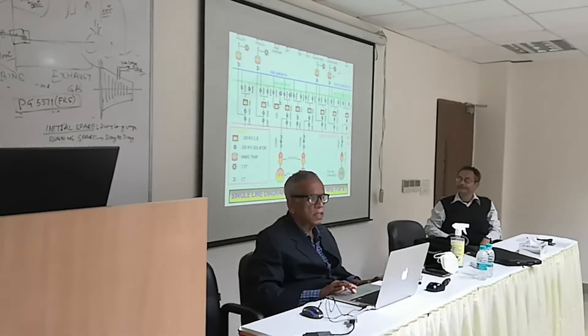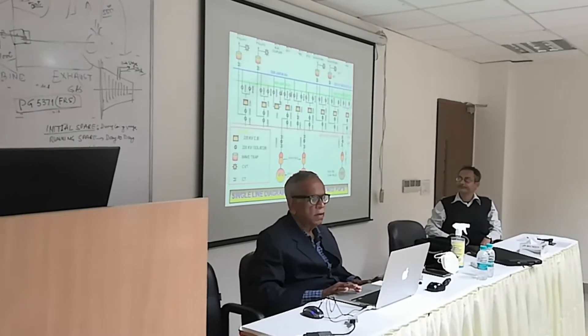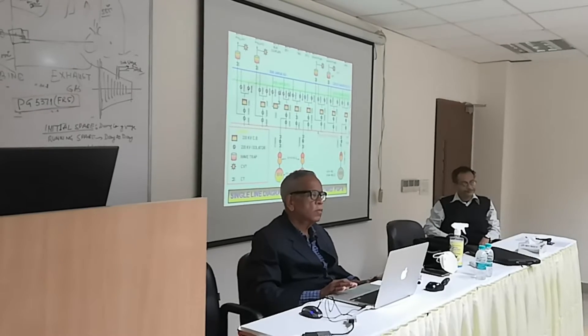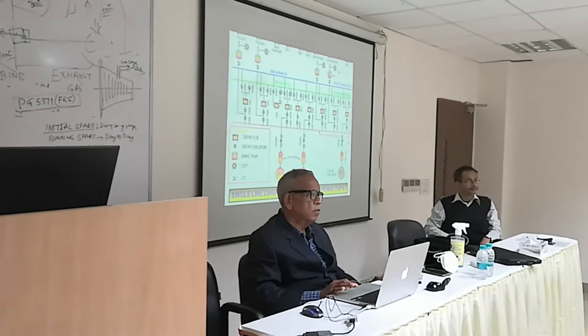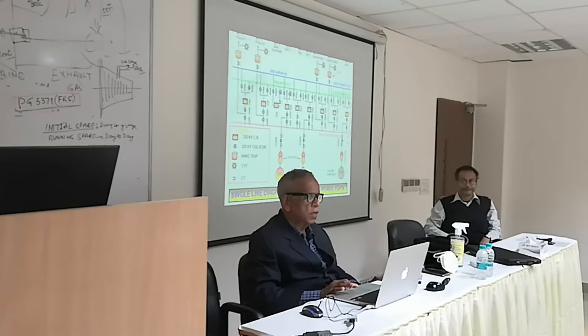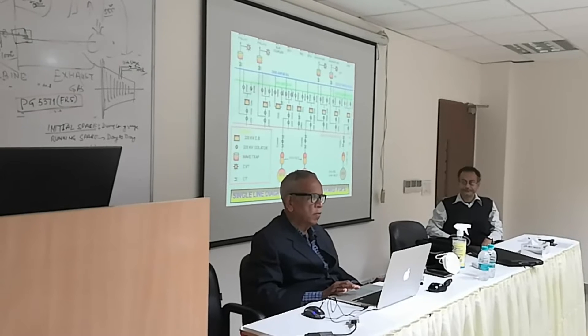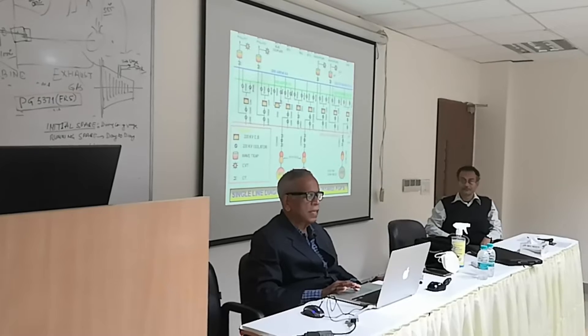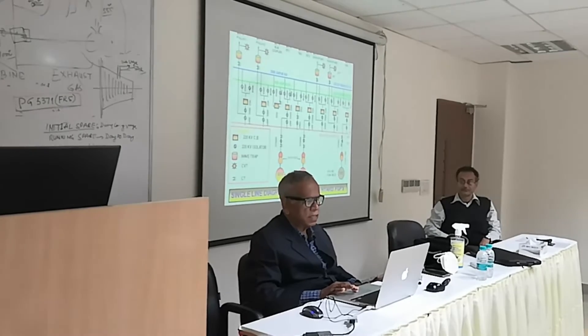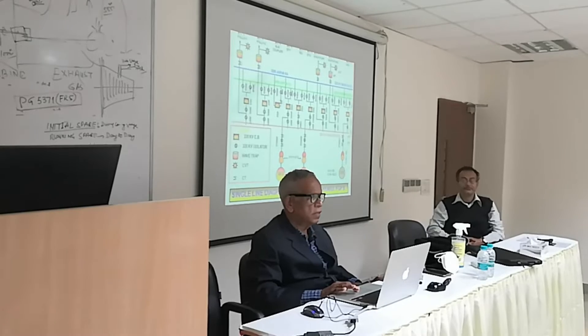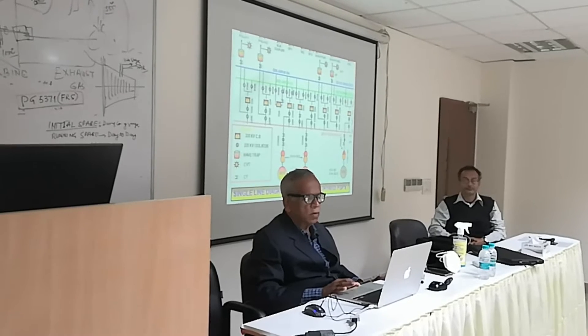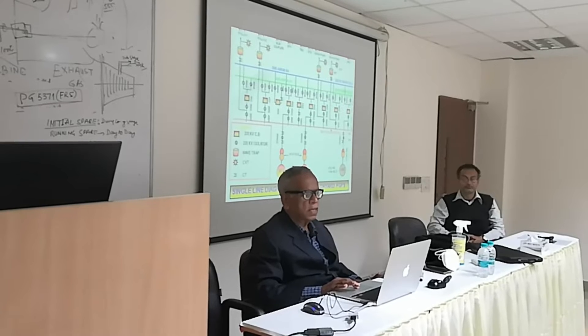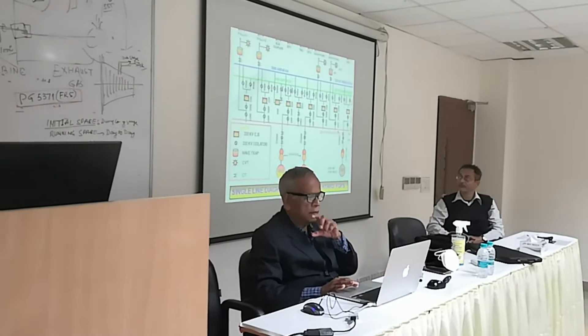Then there is another bus — 220 KV main bus 2. And we also have a transfer bus. The role of the transfer bus is that in case you face any problem with a circuit breaker, such as gas leakage, and you want to carry out maintenance, then you need not stop the generators. There is an alternate route which can be provided by this transfer bus.